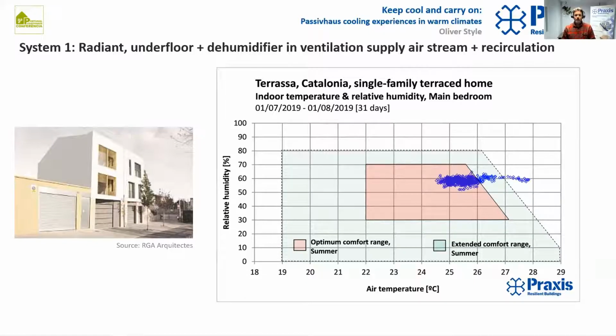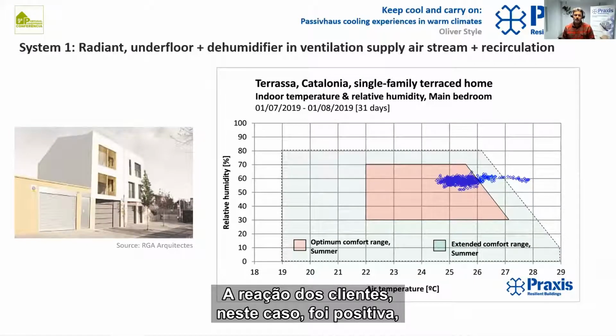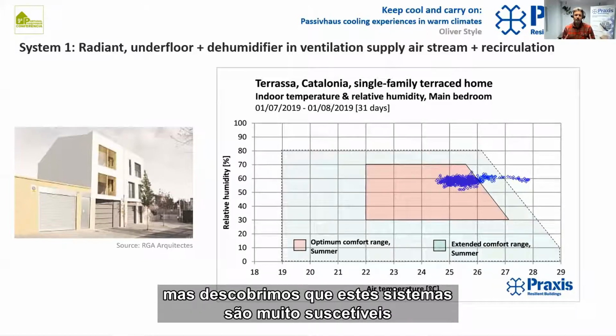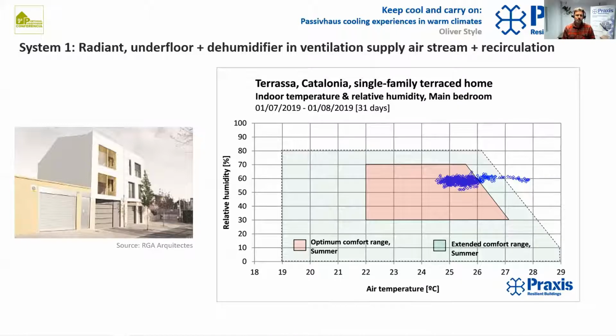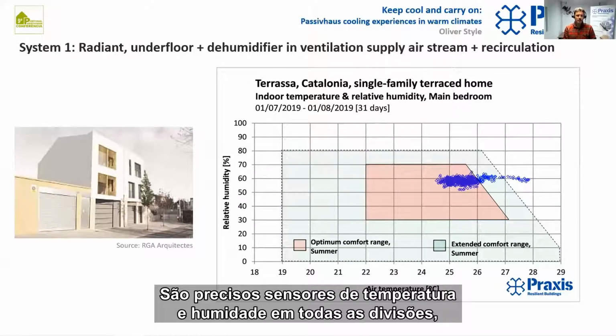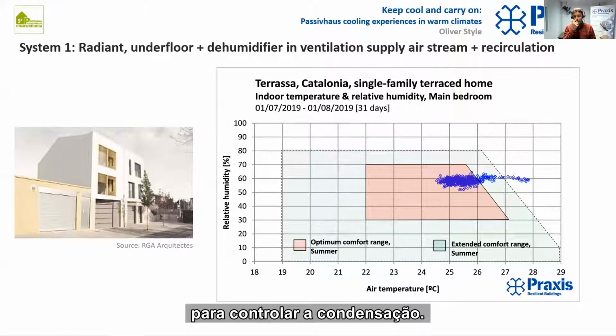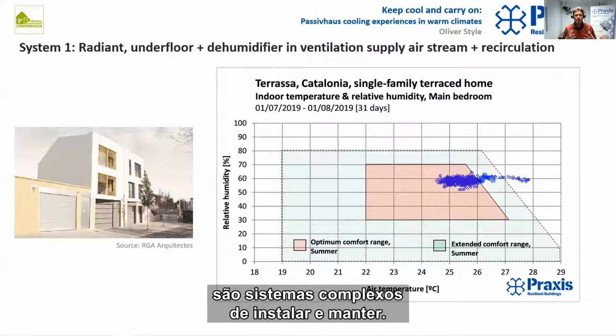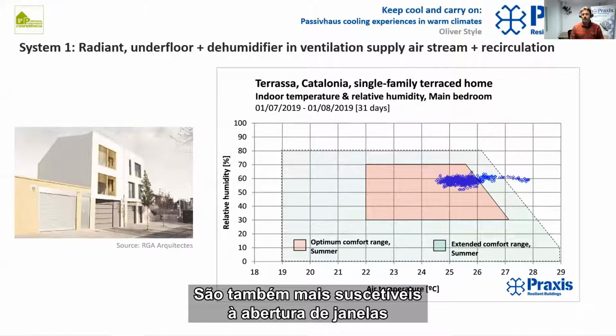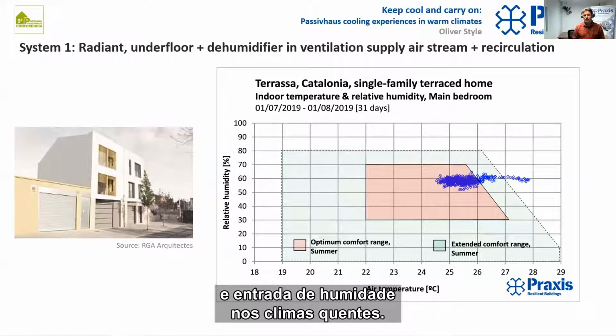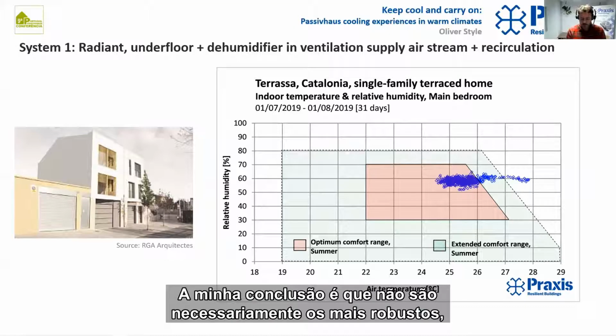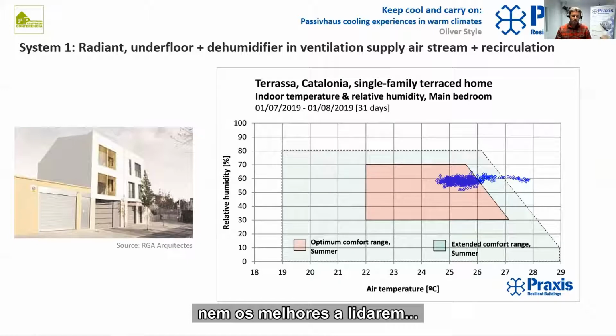The response from our clients in this case was basically positive. What we have found was this kind of system is very susceptible to control system issues. There need to be temperature and humidity sensors in all rooms to control condensation. There can be more maintenance problems. These are more complex systems to commission and to maintain. They're also more susceptible to people opening windows and humidity coming in warm climates. So, my conclusion is that they're not necessarily the most robust, and they're not always the best at dealing with peak heat wave conditions.